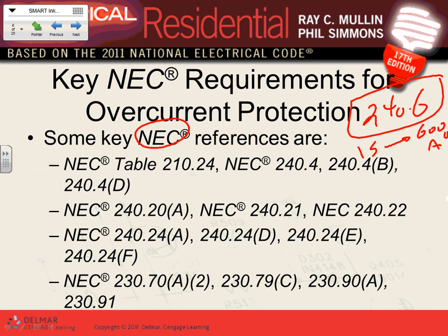Now, you're going to hear me, Andrew, my friend, later on talk about adjustable circuit breakers. The limit on the adjustable circuit breakers, which typically start making sense when you go 600 amps or higher. If your system is not 600 amps or higher, you're most likely looking at fixed circuit breakers like these, non-adjustable. You can't adjust it. The adjustable ones, you can tweak 1,000 amp and make it 800, or make it 750, or make it 533. Well, I'm exaggerating here. 550. Tweak them down, right?